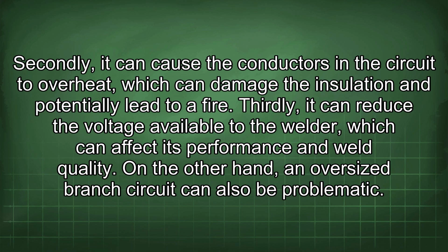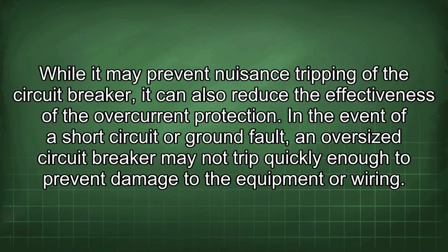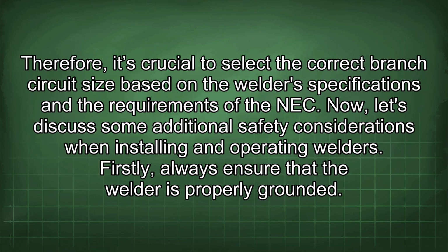On the other hand, an oversized branch circuit can also be problematic. While it may prevent nuisance tripping of the circuit breaker, it can also reduce the effectiveness of the overcurrent protection. In the event of a short circuit or ground fault, an oversized circuit breaker may not trip quickly enough to prevent damage to the equipment or wiring.